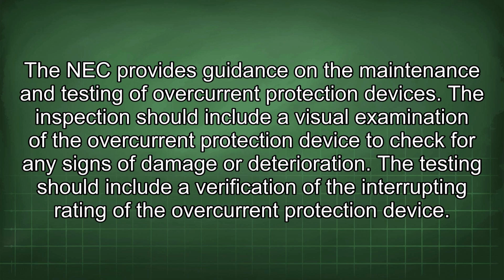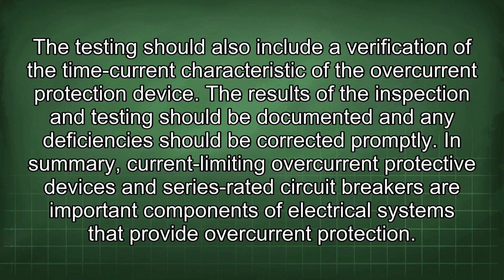deterioration. The testing should include a verification of the interrupting rating of the overcurrent protection device. The testing should also include a verification of the time current characteristic of the overcurrent protection device. The results of the inspection and testing should be documented, and any deficiencies should be corrected promptly.